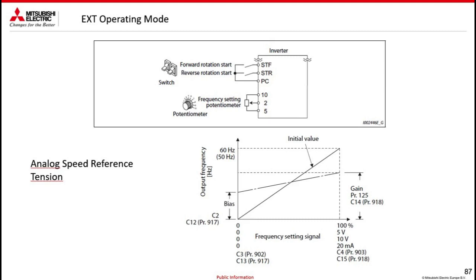All analog set point inputs and outputs are calibratable. What does it mean? It means that if I want to define that the signal is not from 0 to 5 volts, but is for example from 1 volt to 4 volts maximum, I can do it. If I want to define that the starting frequency is not 0 but is 20 Hz, I can do it. The same with the maximum frequency. Obviously, instead of 50 Hz, if I want it to be 40, 60 or 100 Hz, I can do whatever I want.